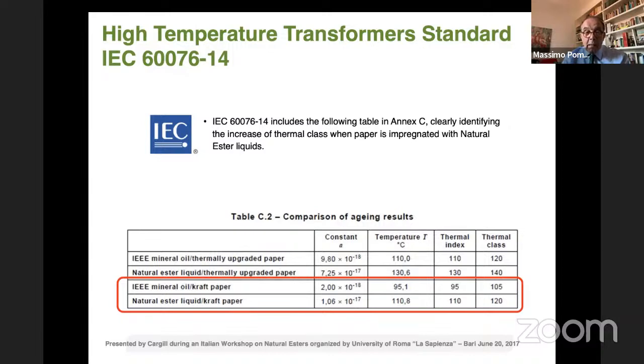For natural ester liquid and kraft paper, the thermal class is 120. This means your transformer may work at a higher temperature. It means you can load your transformer much more. You can overpass some moments when your system needs to be overloaded.